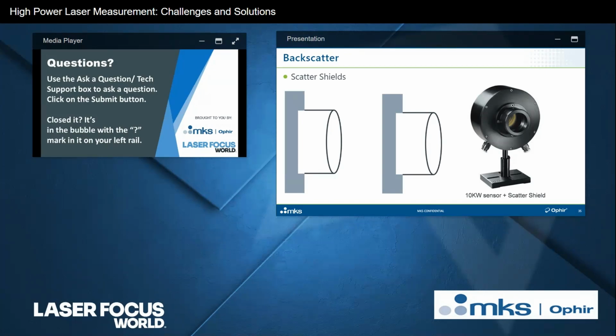So we offer at Ophir, and I imagine other manufacturers have something similar, a scatter shield as an optional accessory. And basically, I apologize for my artistic skills here, but I hope it gets the point across. What basically happens is you attach it to the surface in front of the aperture, and then the beam comes in, those 5 or 10 or whatever percent of the power gets diffusely back reflected out. Much of that meets the inner surface of that scatter shield, and much of that gets reflected back into the aperture of the sensor for a second go. So instead of 10% being reflected, I know that with the Ophir scatter shield, something like 70% of that backscattered power ends up getting reabsorbed. So we're significantly cutting down the backscatter.